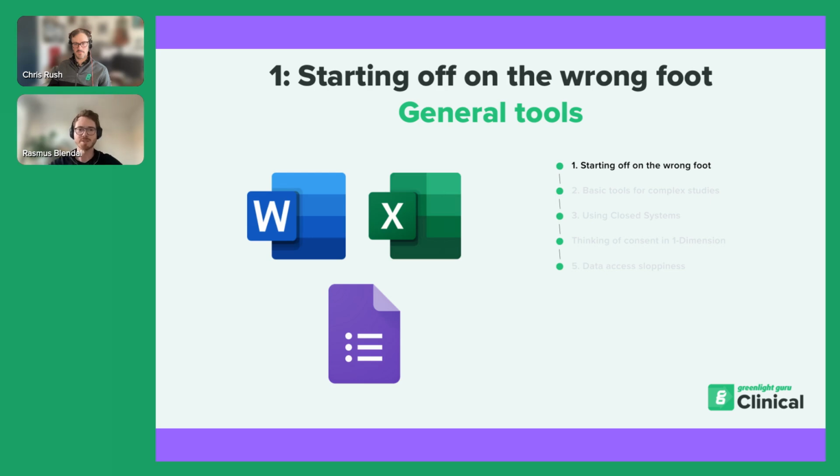The main issue here has to do with validation. And validation has become a very big topic ever since the introduction of ISO 14155 2020, where in section 7.8.3, that's a lot of numbers, it speaks to the responsibilities of sponsors as it pertains to computerized systems. Here they mention a lot about validation of the system you're using for clinical activities. And this goes for any sort of clinical activity you're doing. So long as you want to submit it to a competent authority, it must be validated.